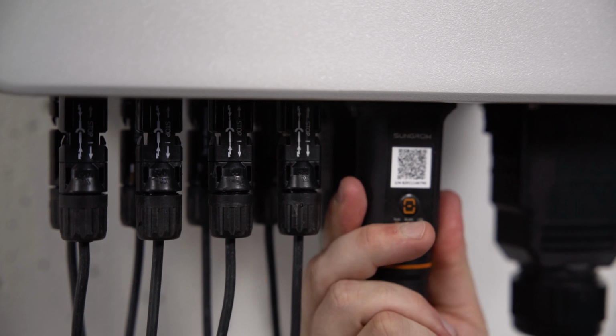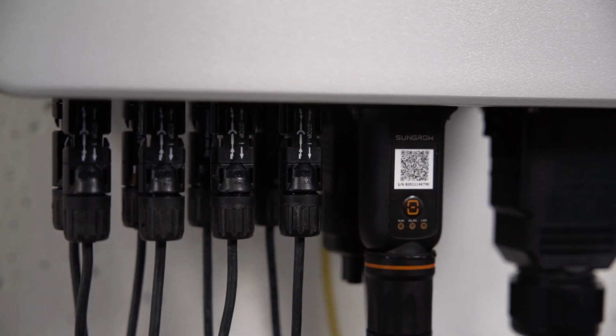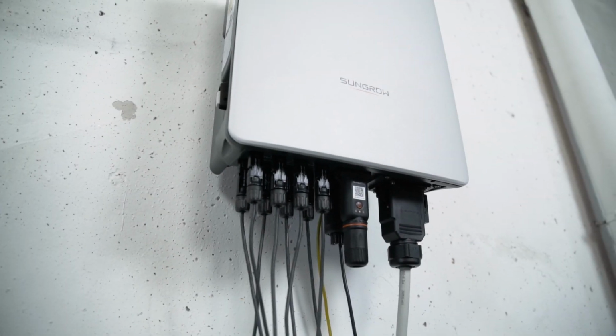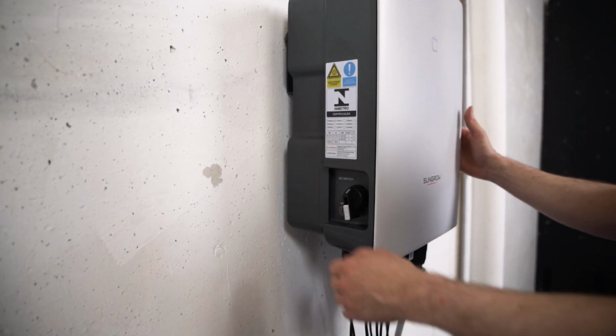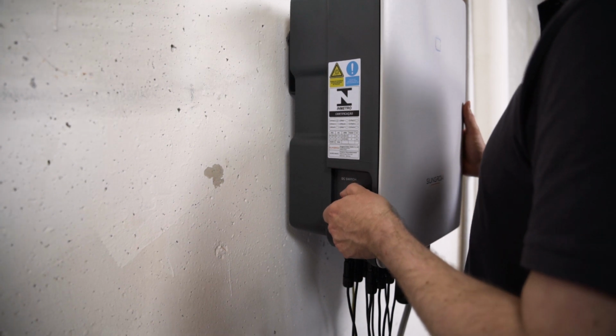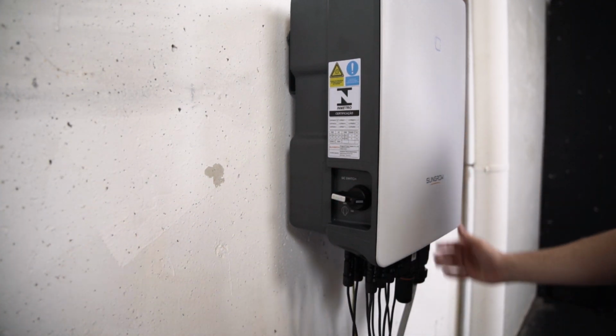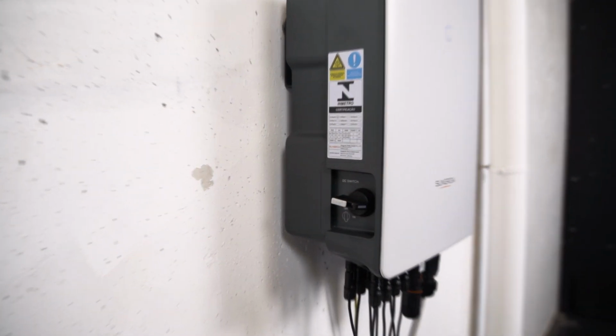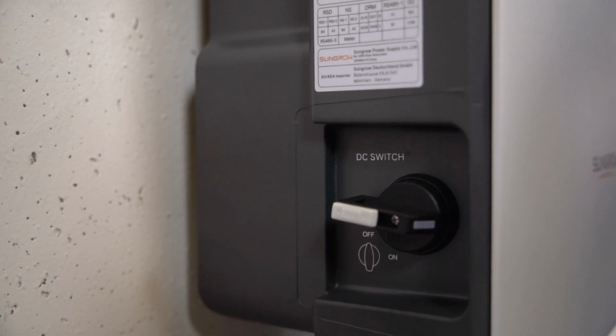If you want to use Wi-Fi, it's even easier. Simply connect the module to the inverter. That's it. The installation is done. Now it's time for commissioning. First, you have to set the DC switch of the inverter to the on position to connect the inverter to the PV generator. Next, you have to switch on the AC circuit breaker.